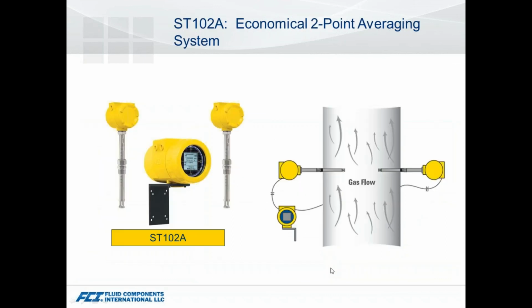So one of the first things to look at is this ST102A. Now we're looking at a 2-point averaging system, and from my experience, up to about 40 inches in line size, think a round diameter duct or pipe, this is a very good approach to providing you a higher accurate reading in these larger line sizes. It's more economical as well compared to our fully featured device. So you get all those benefits of the ST100 with the ability to improve your accuracy.